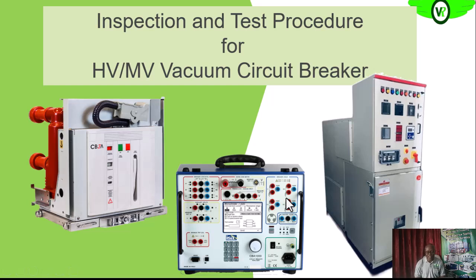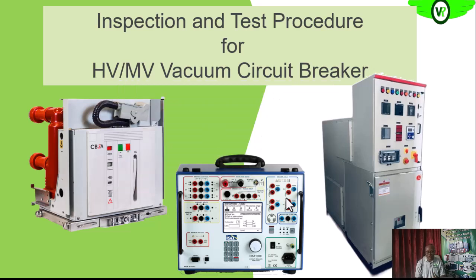Next on the inspection and testing series on electrical equipment, we are going to be looking at the medium voltage and the high voltage vacuum circuit breaker. In a vacuum circuit breaker, the arc quenching medium is the vacuum, between the contacts in the vacuum bottle or capsule.